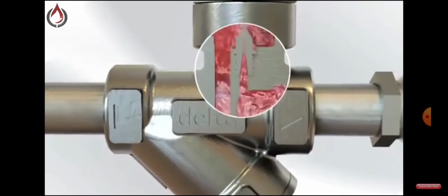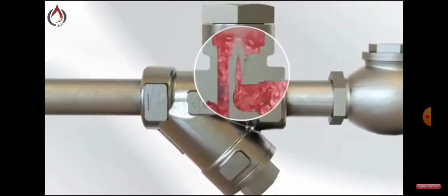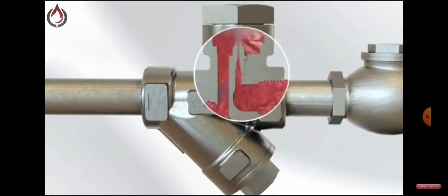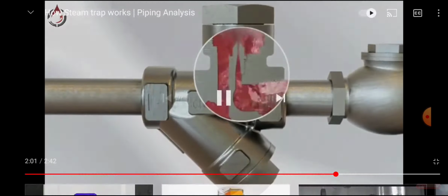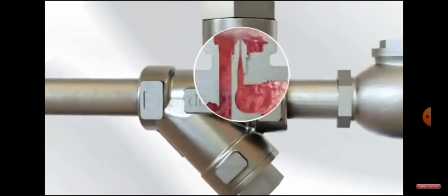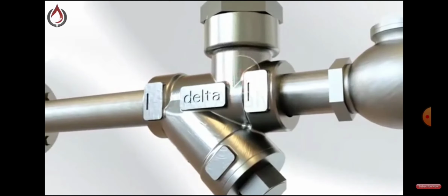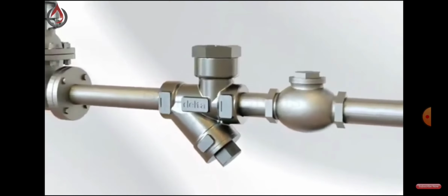As the pressure or load in the steam system rises or falls, the back pressure that is constantly changing at the mouth of the venturi also rises or falls. This action gives the Delta venturi orifice steam trap the ability to easily manage discharging varying condensate loads in a steam trap that has no moving parts, while still keeping the steam in the system.